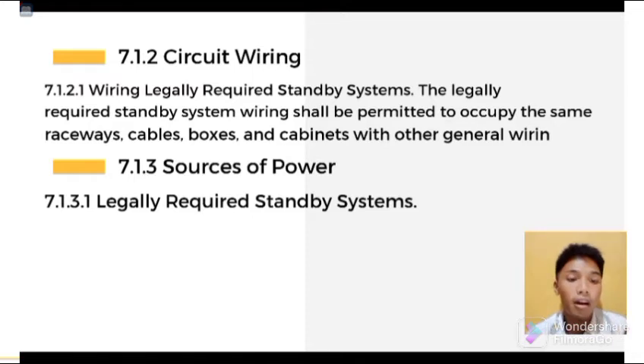4. Battery power. Where a storage battery is used for control or signal power or as the means of starting a prime mover, it shall be suitable for the purpose and shall be equipped with an automatic charging means independent of the generator set. Uninterruptible power supplies.